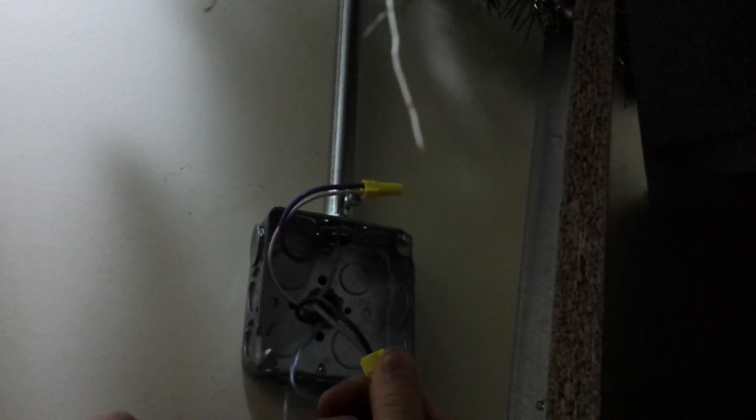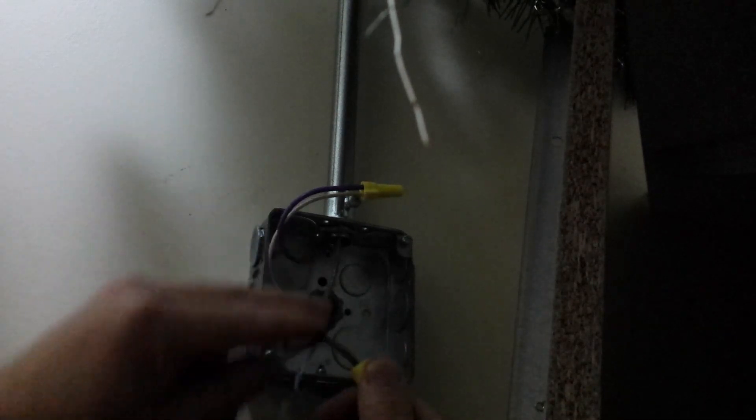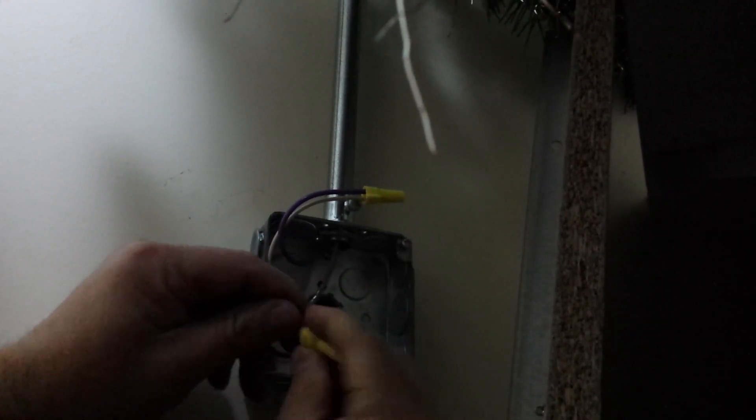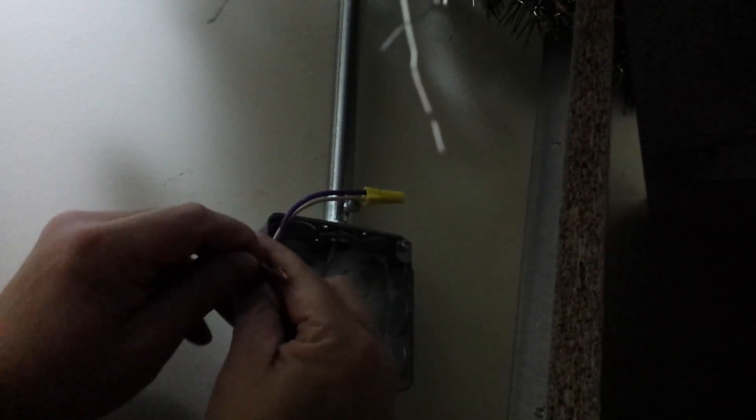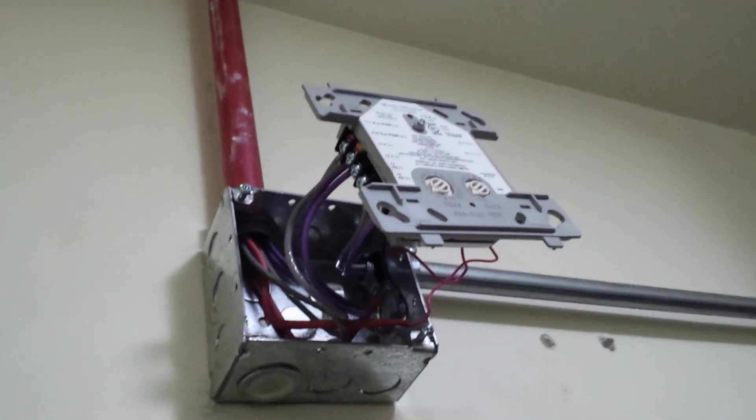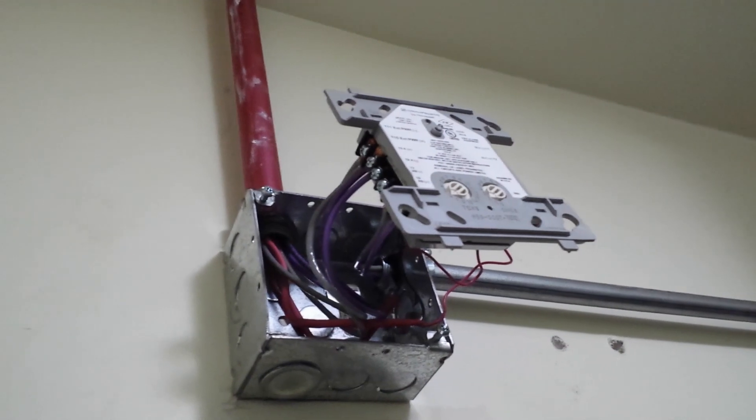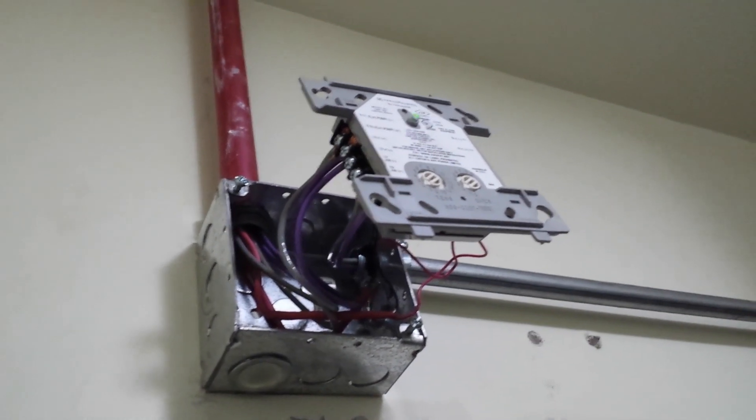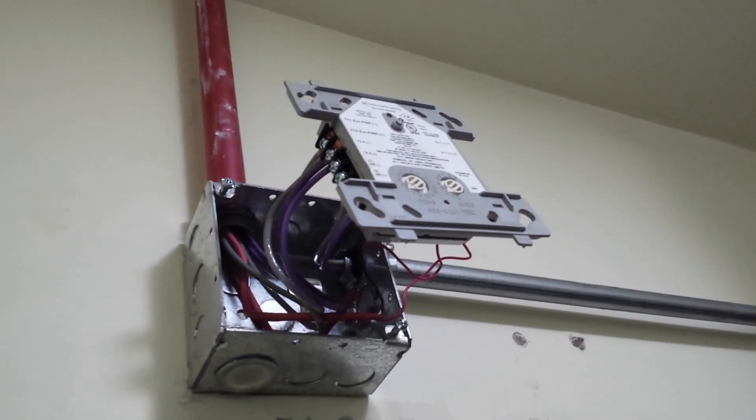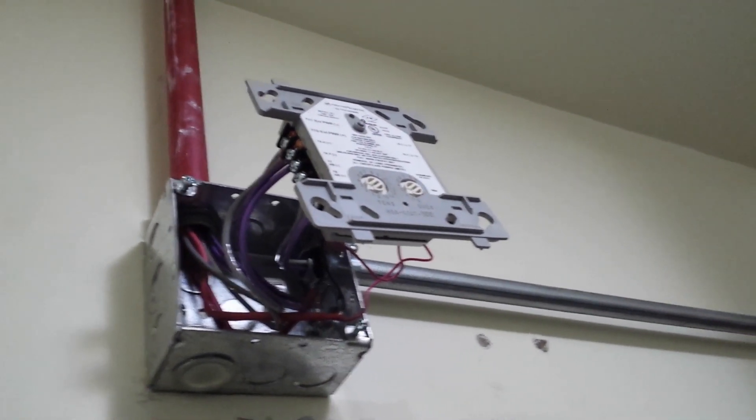The question is how could that happen? Obviously we know now that we probably need to go out and check out the exterior device. We're going to do one quick thing, we're going to go back and disconnect the output side. I'm just going to disconnect it in this lower box because it's a little easier to reach. Purple goes to black, I mean gray goes to black, purple goes to white. Now it's normal. We disconnected the module and now it's normal.